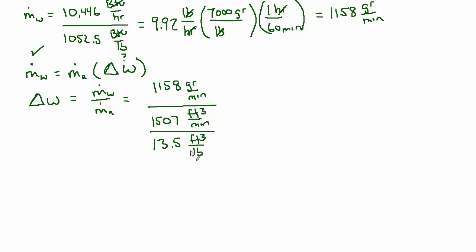And if it turns out that we were way off in this assumption based on what we ultimately find out about the condition of that supply air, then we should go back and iterate on this and use the real specific volume, and you may have to do it a couple times until it starts to converge. But we can be relatively confident that it's not going to be too far away from 13 and a half.